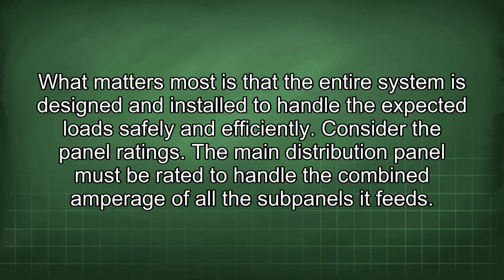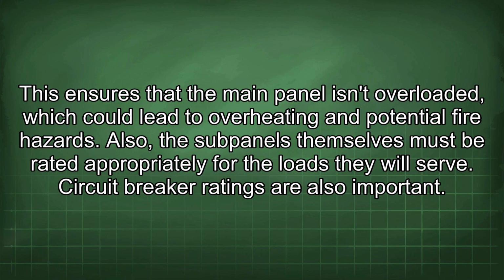The main distribution panel must be rated to handle the combined amperage of all the subpanels it feeds. This ensures that the main panel isn't overloaded, which could lead to overheating and potential fire hazards. Also, the subpanels themselves must be rated appropriately for the loads they will serve.